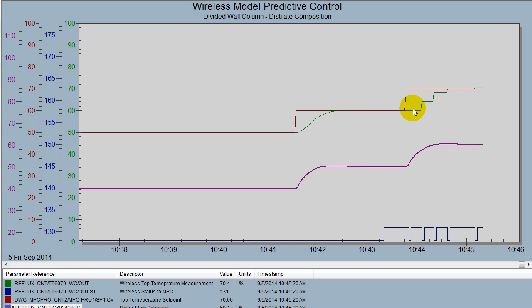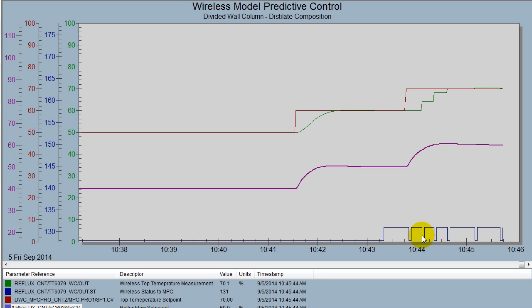In between measurement updates, we are simulating the value. This is based upon the status that the composite is calculating to indicate to model predictive control whether the measurement is new or old. We're changing the status to 'constant' when no new measurement is available. In those time frames, we're simulating the actual temperature based upon the manipulated parameters and the model that is inherent within model predictive control.